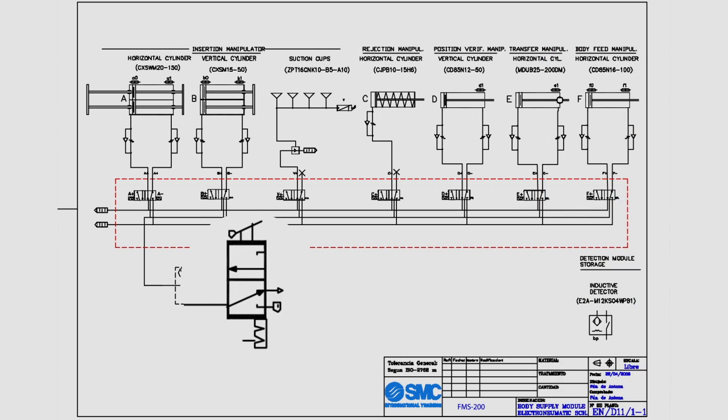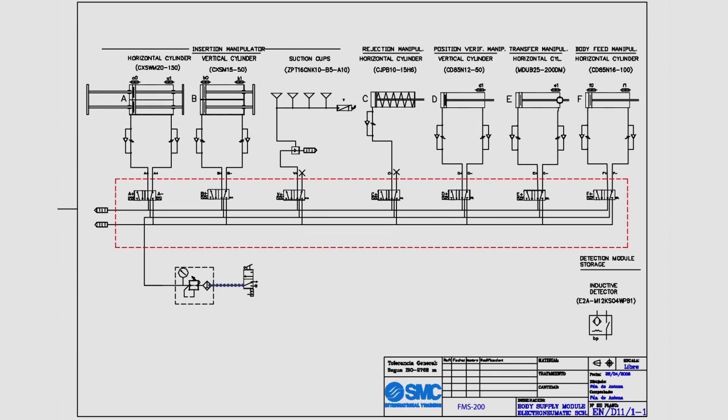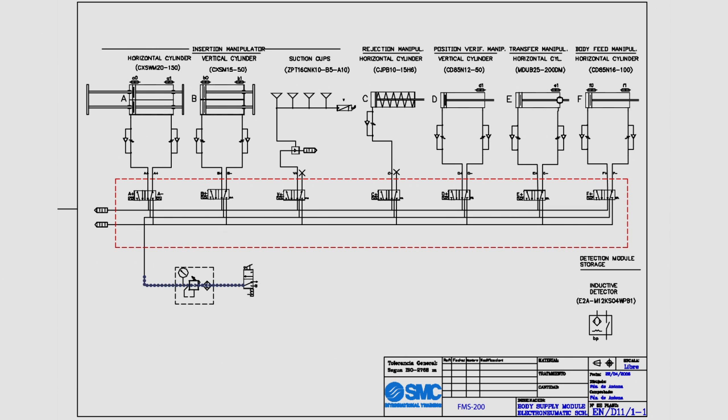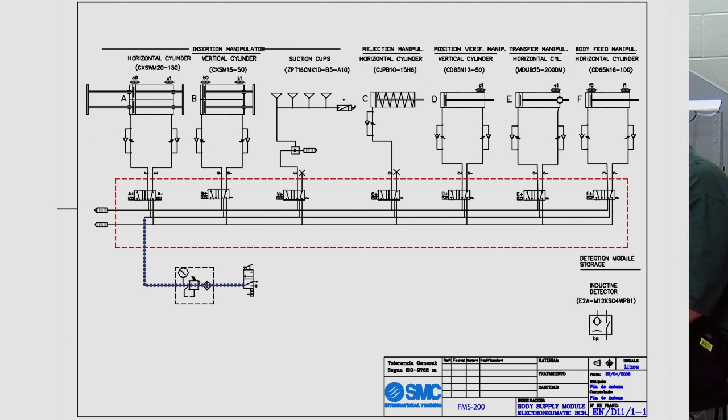We have a hand-operated valve right here which is actually the on-off control for the air so we can turn either the air on or the air off. It then comes into a component known as an FRL which is a filter regulator and lubricator. And then from there you can see it's distributed throughout all of the actuators in the actual station.